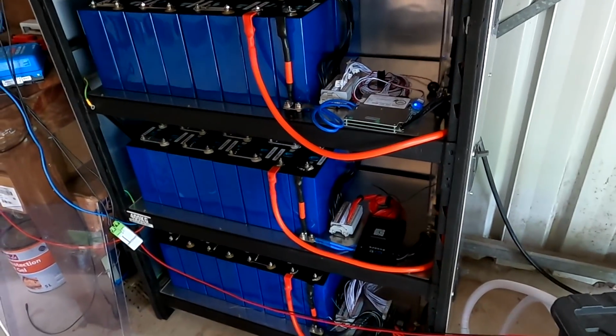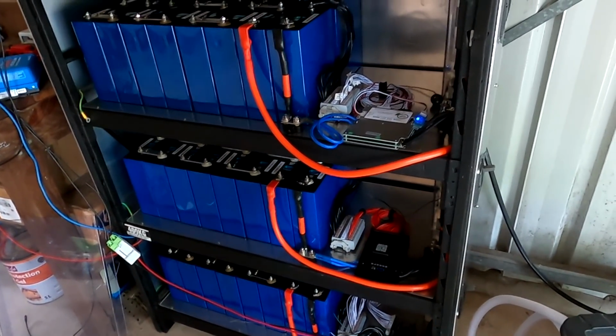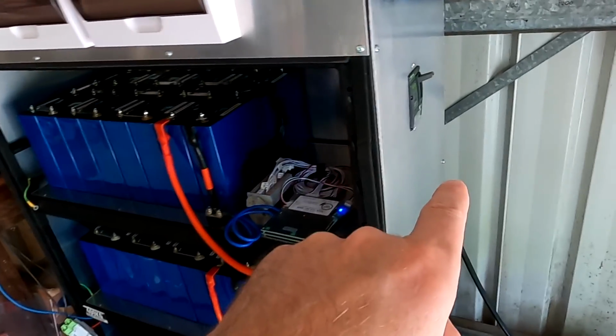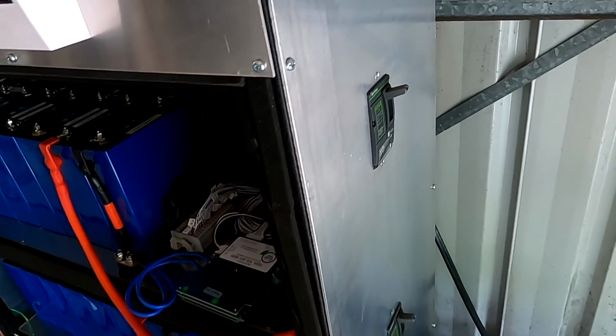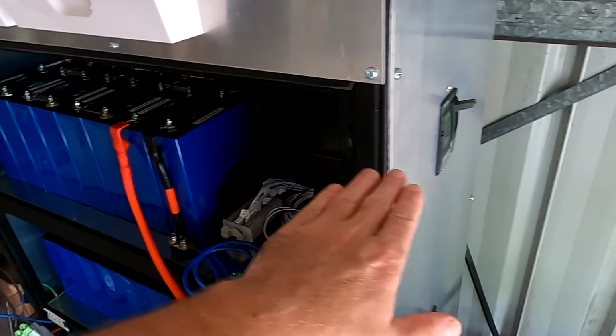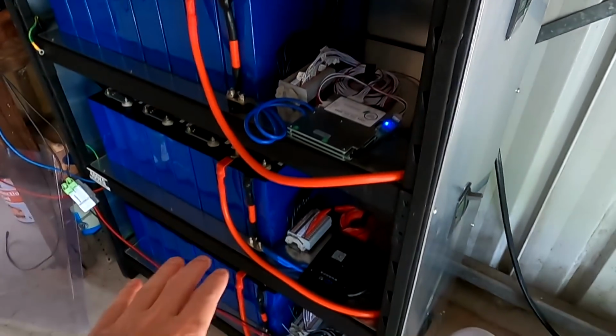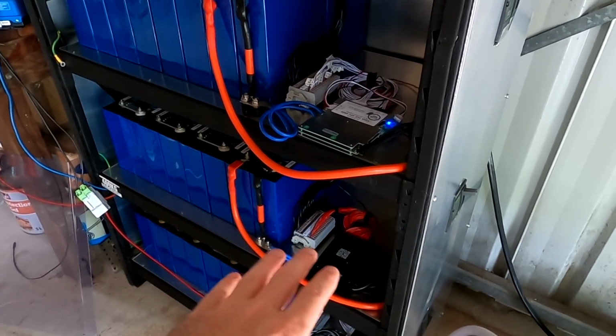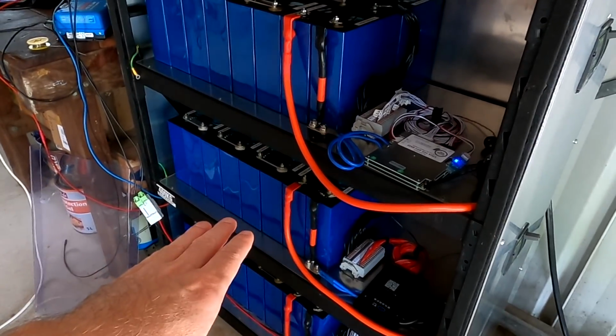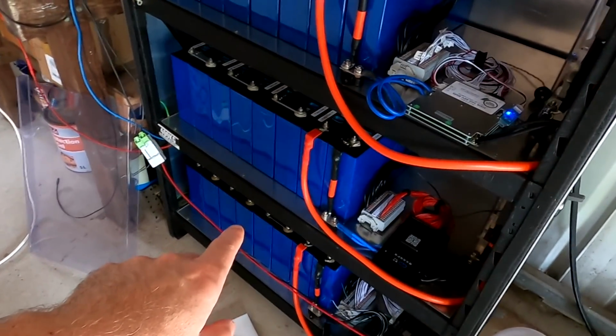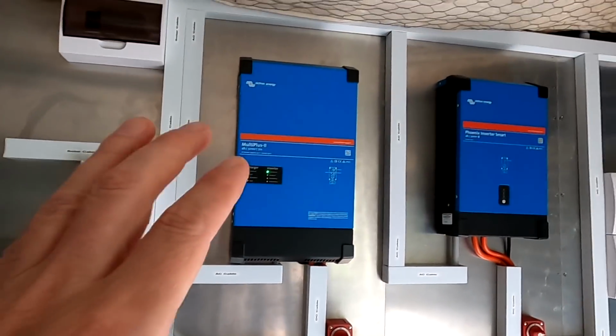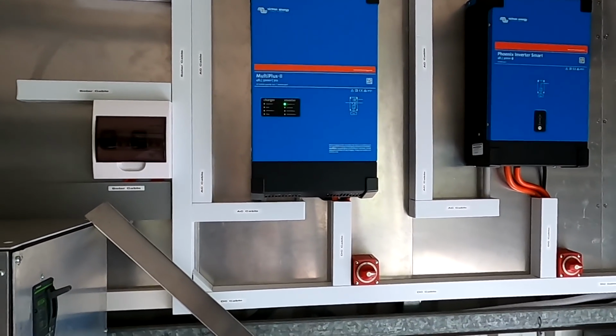So we should see fairly equal currents going into the batteries, assuming they are on the same state of charge. This shows again the big advantage of having 3 separate battery banks with separate BMSs and separate switches or circuit breakers. We can just turn off one battery bank completely and the whole system runs from the remaining battery banks. I can even turn off 2 of these battery banks and one would be capable of running the whole system with 2 inverters here just fine.